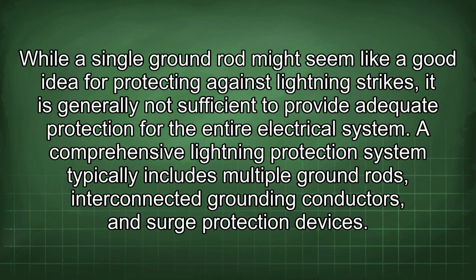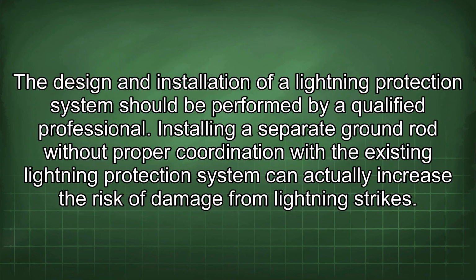While a single ground rod might seem like a good idea for protecting against lightning strikes, it is generally not sufficient to provide adequate protection for the entire electrical system. A comprehensive lightning protection system typically includes multiple ground rods, interconnected grounding conductors, and surge protection devices. The design and installation of a lightning protection system should be performed by a qualified professional.